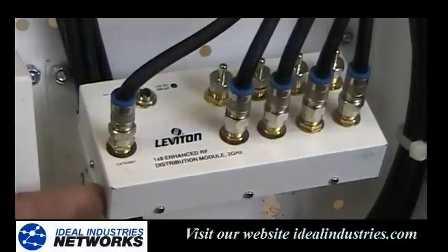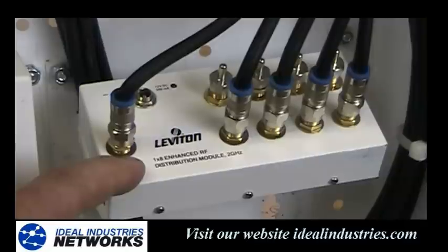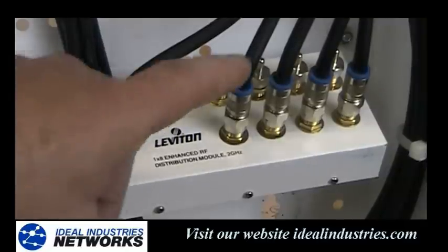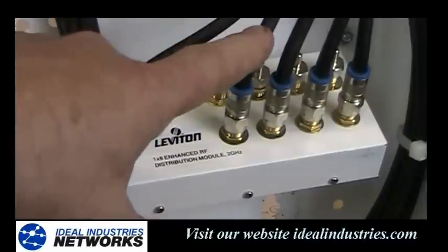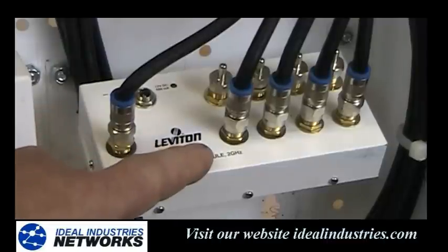Now, there is an adjustment on the amplifier for how much you're going to amp it, and it's right here. There's an opening on the side here, and we can get a screwdriver in there and adjust the gain of the amp upwards of an additional 20 dB if we need that, depending on how long our runs are in the house, in order to make sure we get a good quality picture out of it at the outlet in the room.